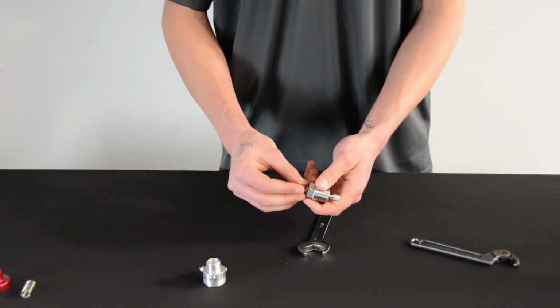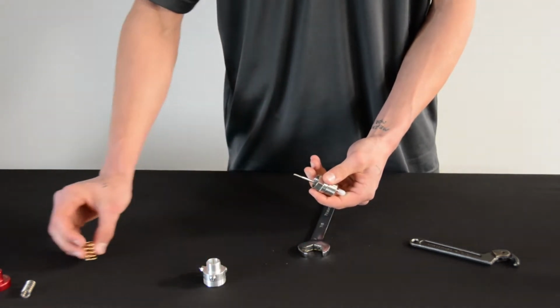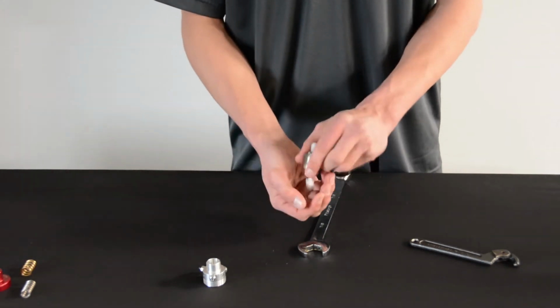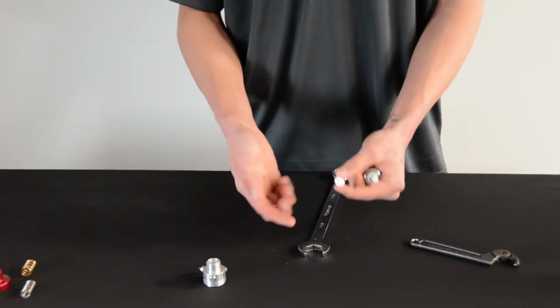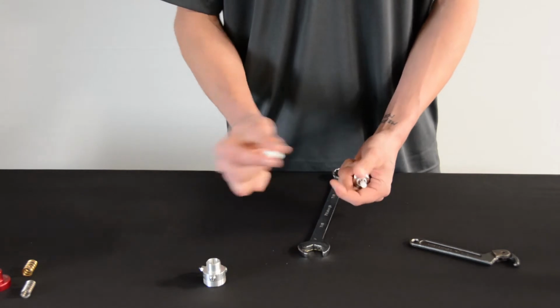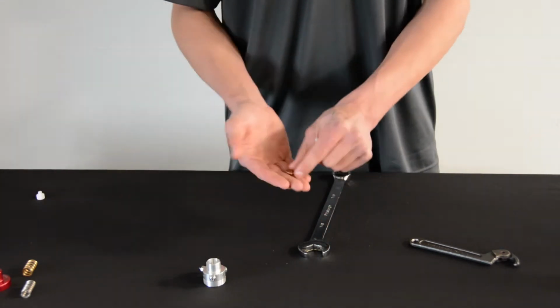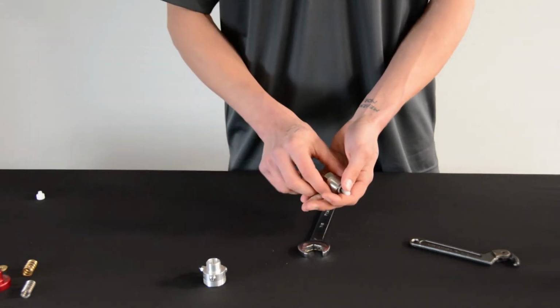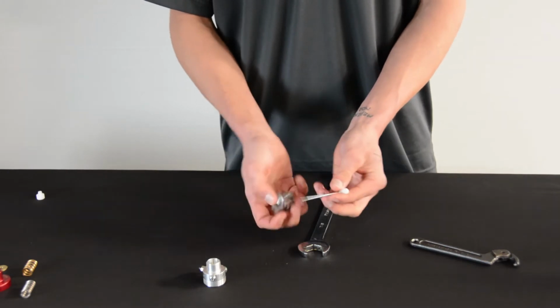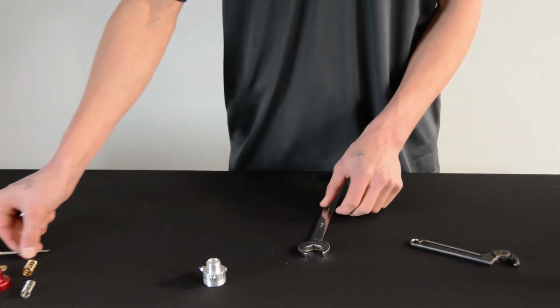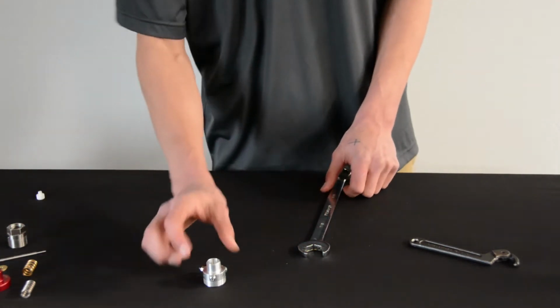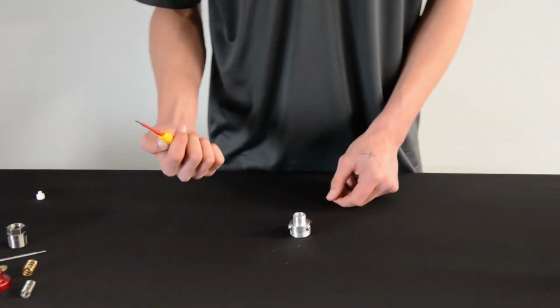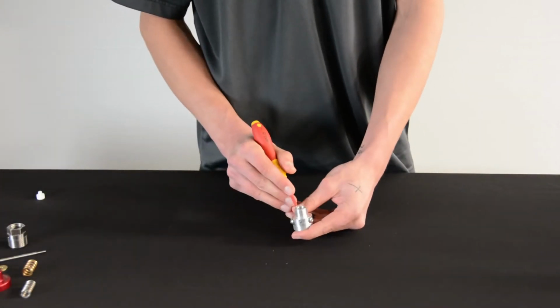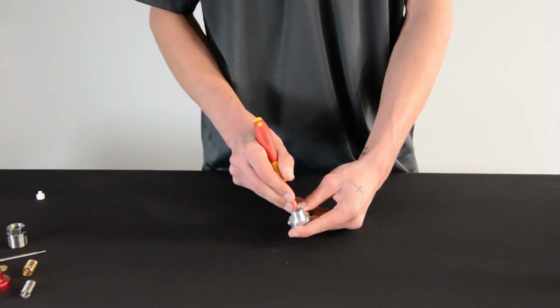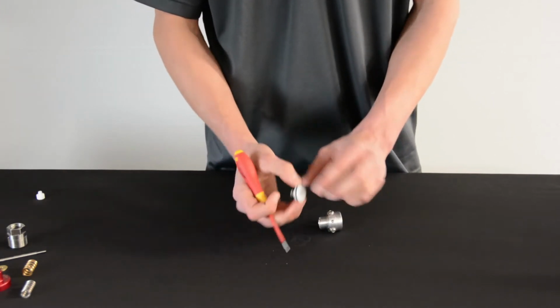When you do this, your packing spring will come out, and you can put that off to the side, and your packing and packing washer will come out. The packing will then be discarded, but your packing washer will be kept. You can then remove the shaft from the valve body and put that off to the side, as well as the valve body. Then take a small screwdriver and push the piston out of the piston body.